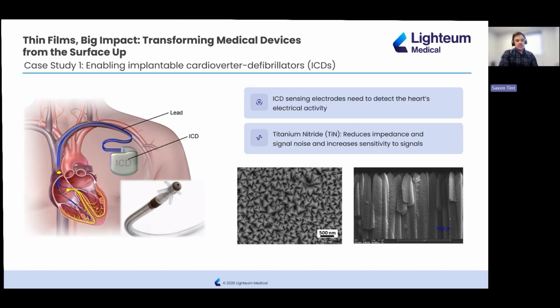Those electrodes, the part that does the sensing is not the wire or the device. It's the electrode surface. So those electrodes are coated with titanium nitride, that brown-looking coating. Now, titanium nitride dramatically reduces the impedance of the electrode and increases its sensitivity to tiny electrical signals coming out from your heart.